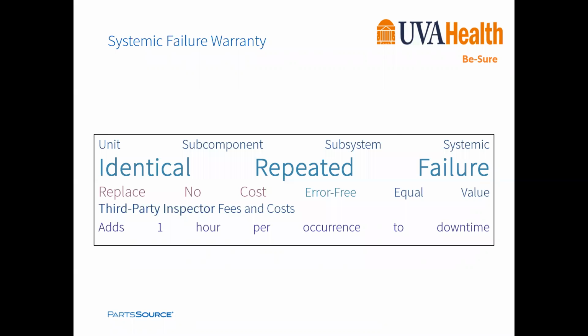This is an identical and repeated failure within a unit, subcomponent, or subsystem. What we do is add 1 hour per occurrence to that. This allows us, once we identify these systemic failures, to very rapidly escalate them on our downtime calculation to motivate the vendor to take them seriously and resolve the systemic failure.